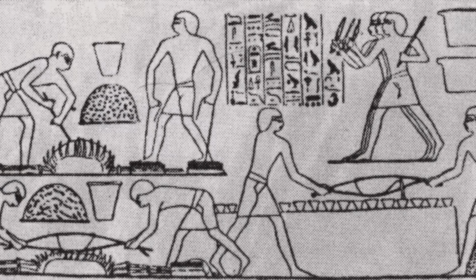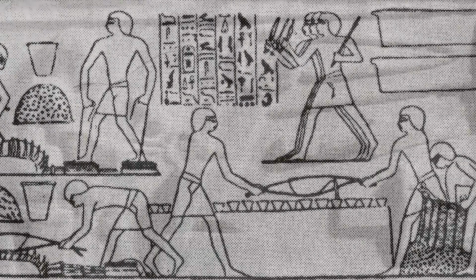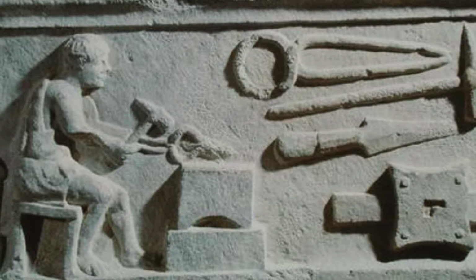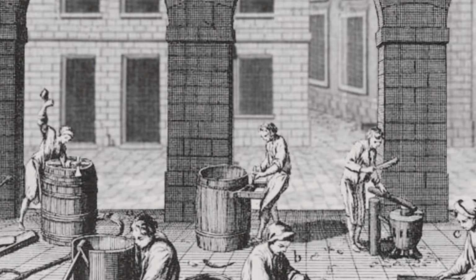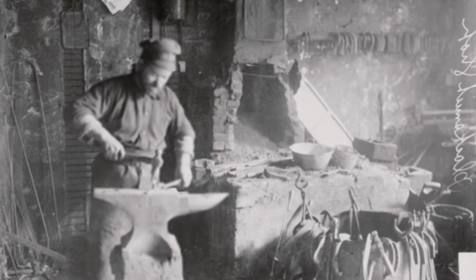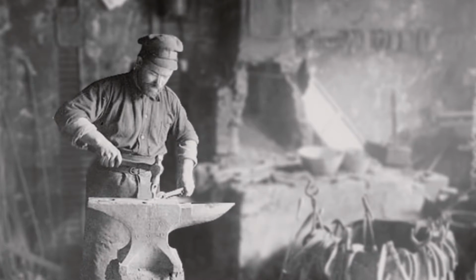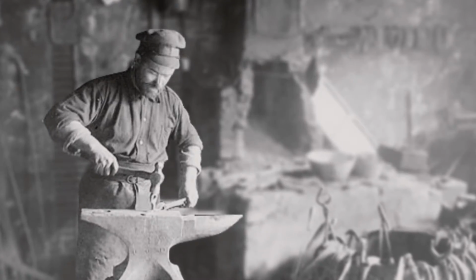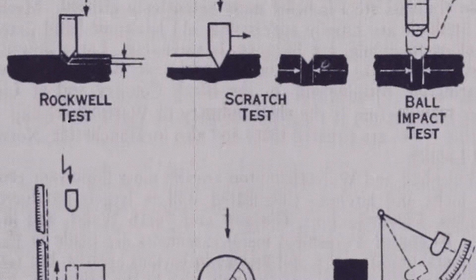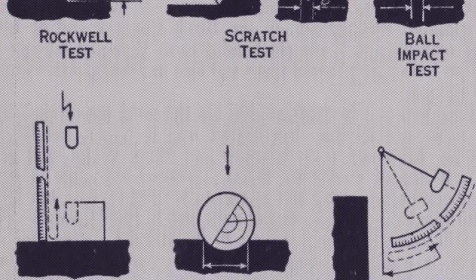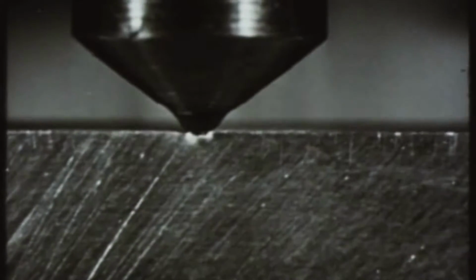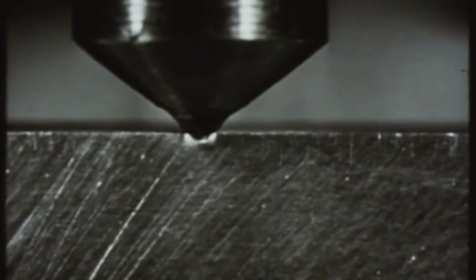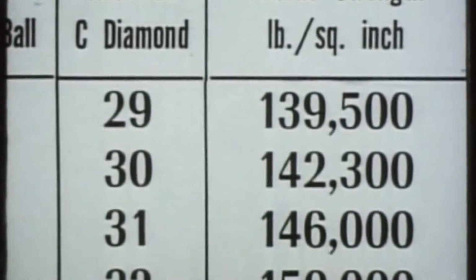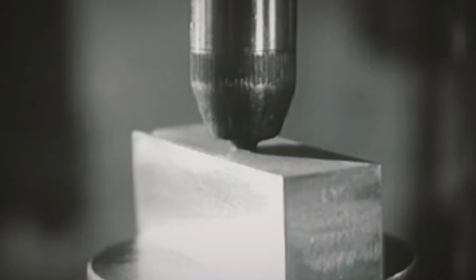From the moment people started alloying steel, they thought of ways to measure its hardness. The first testing method was more or less based on scratching the surface of an alloyed piece. How easy it was to scratch the surface often defined the hardness. This test soon proved a very unreliable method, and the need grew for a traceable and repeatable parameter. As time passed, engineers started to define material hardness by penetration, and later on, methods evolved into the measure of the amount of resistance that different materials present to penetration by a specifically shaped object.